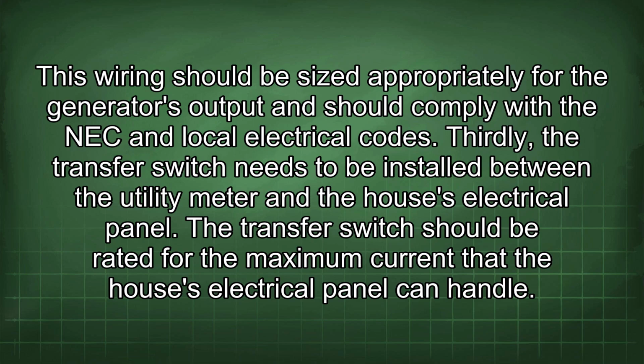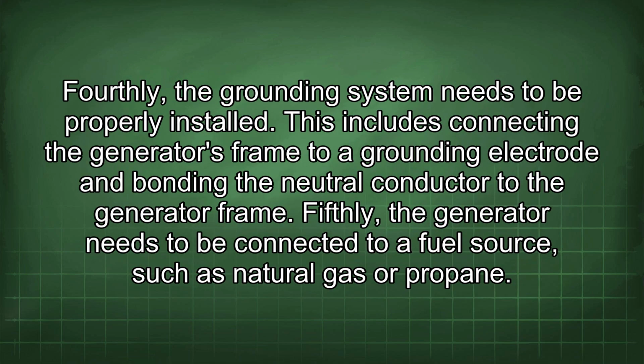This wiring should be sized appropriately for the generator's output and should comply with the NEC and local electrical codes. Thirdly, the transfer switch needs to be installed between the utility meter and the house's electrical panel. The transfer switch should be rated for the maximum current that the house's electrical panel can handle. Fourthly, the grounding system needs to be properly installed. This includes connecting the generator's frame to a grounding electrode and bonding the neutral conductor to the generator frame.